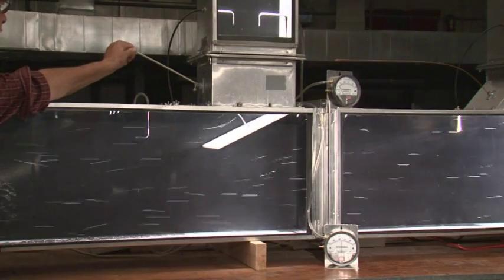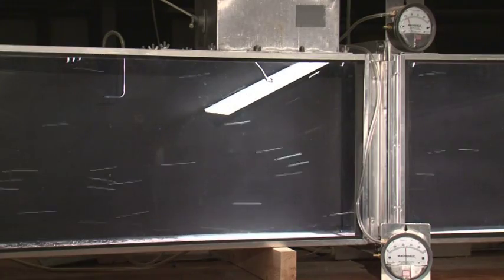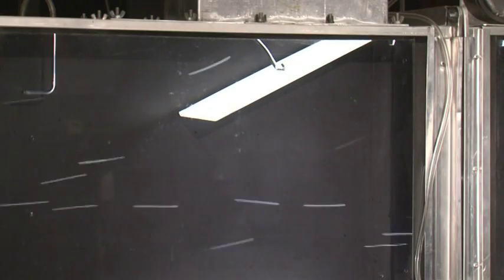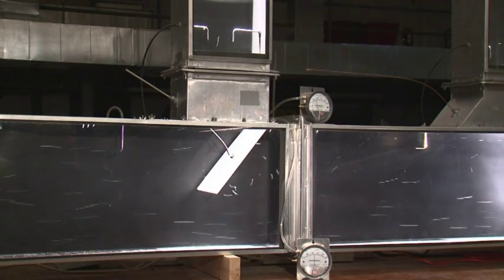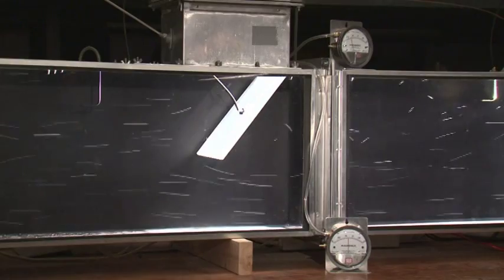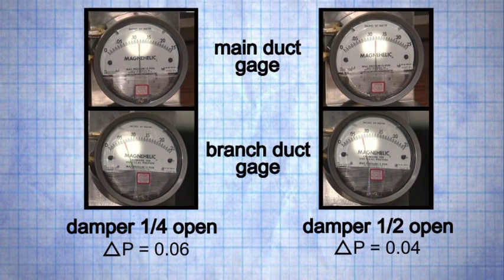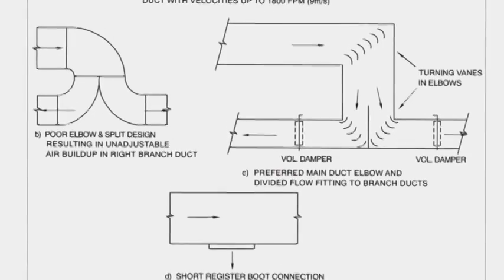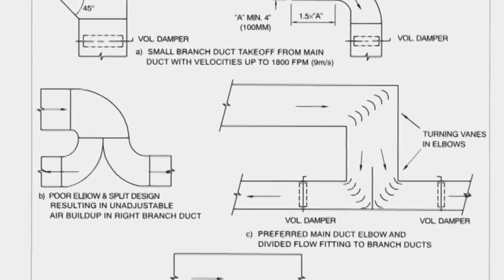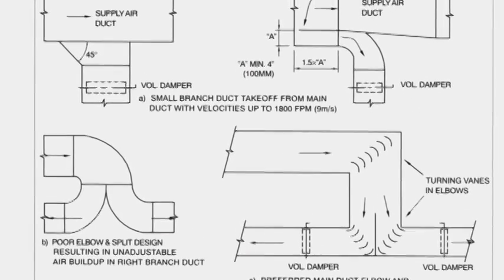As this type of damper is opened into the main duct's airstream, air is literally scooped into the branch duct. While some air balancer contractors have noted that this type of damper makes duct balancing easier, note how bubbles in the area downstream of the in-duct damper are turbulent and airflow is severely restricted. The turbulent airflow behind the damper is an illustrative proxy for duct system pressure loss. From a duct design perspective, it is better to specify that dampers be installed in the branch ducts where air volume can be controlled without introducing interference into the airflow of the main duct.